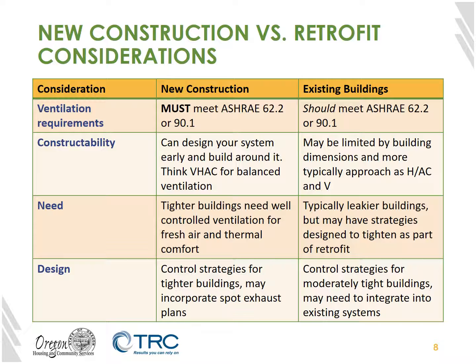The control strategy is going to be a little different for existing buildings. But again, because we're likely tightening these buildings by performing some of these other weatherization measures, we may still have some of those considerations. What we're really going to be faced with, however, in existing buildings are things like, what is the ductwork like for the existing heating and cooling system? How about the chaseways and the building cavities? Do we actually have room to run a heat recovery ventilator, or do we need to tie it in to the central heating and cooling system to make it all work? So different considerations, different needs, different designs between existing and new construction buildings.